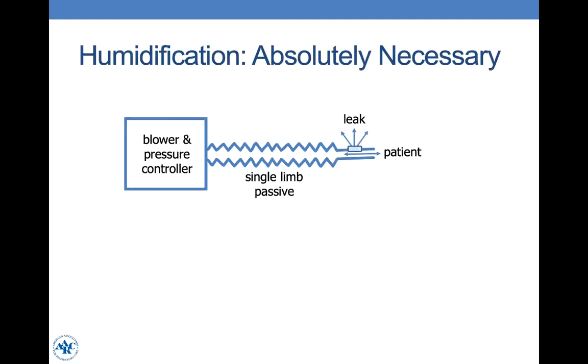Because we are using the device invasively attached to an endotracheal tube, it is important that the inspired gas is humidified. We can do this with an active humidifier, such as we would use on an ICU ventilator, or we can use a heat and moisture exchanger. I would suggest considering a heat and moisture exchanging filter device, or HMEF, which also provides additional safety by filtering aerosols exhaled from the patient into the environment.